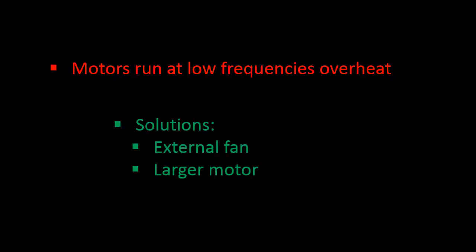Even with voltage control to avoid saturation, the motor will still tend to overheat at low frequencies. Using an external fan, or upgrading to a motor of larger physical dimensions, can help with this by increasing the airflow over the coils.